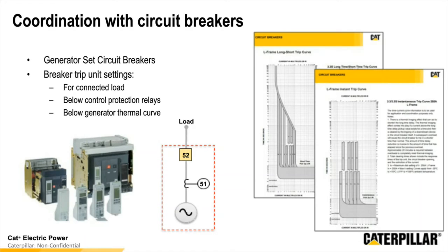You want to set those trip settings, as we talked about just a minute ago, more focused on the load. So you're going to make the decisions on what settings to use based on the load that's connected to it. But you also want to be below the control protection relays and below those generator thermal curves. As we talked about earlier, we'll be looking at coordinating these as we go forward, and we want to make sure that we're to what we would consider the left on the graph as we continue to move down the path, even though we're providing enough energy for the load, but we're also protecting the system.